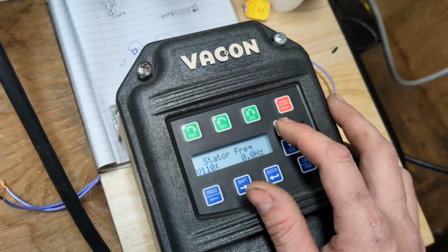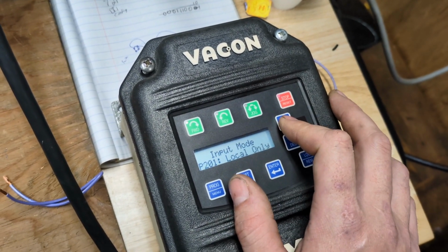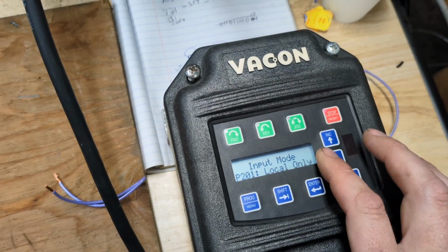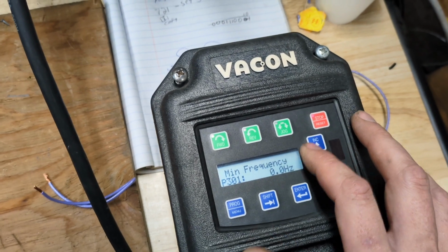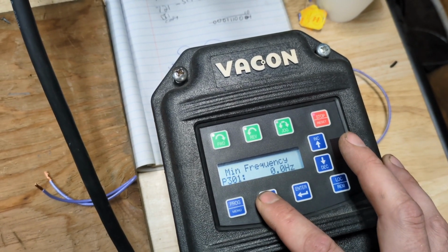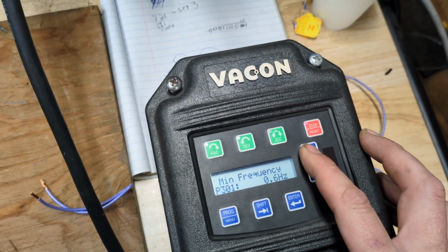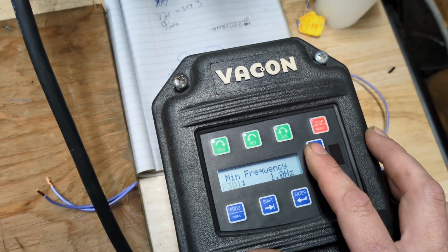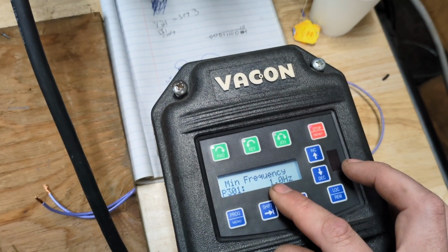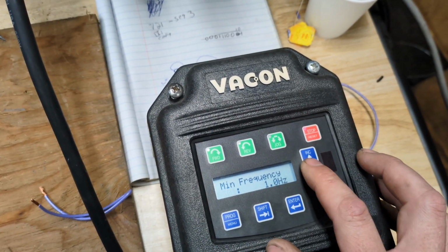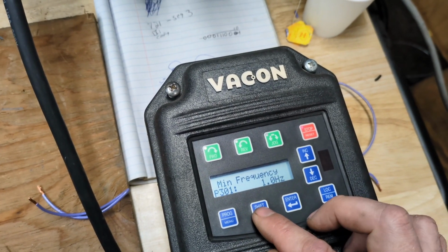Anyone can enter level 1 simply with just pressing program, and they can change whatever they want. So let's say we want to change something here in level 1. We'll change minimum frequency. So we go there, press shift, you'll see it start blinking. We can change it. We'll change it to 1 for now. We hit enter to save, and it tells you store. If you press shift and then you change it to 1.1 and then you hit shift again, you lose everything.